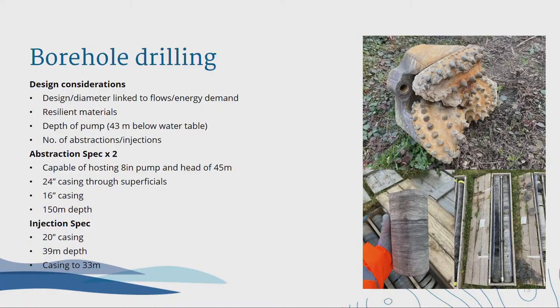Then thinking about the number of abstractions and injections you want. At Gateshead, because the abstractions are relatively shallow at 150 metres, they had 2 of them because they wanted a bit of flexibility and resilience on the system. So it won't need to run at peak demand all the time. The peak demand of that system will be 6 megawatts. And it means that if they want to work on one of the boreholes or one of the pumps, they can do that and set the other one aside.